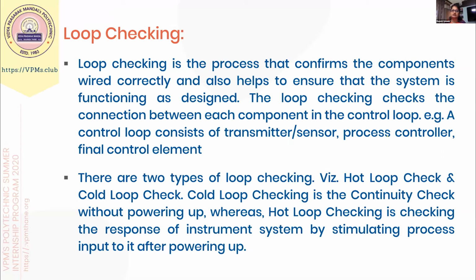The loop checking checks the connection between each component in the control loop. That is, a control loop consists of a sensor, the process controller and the final control element. So whether the loop is working in the right manner, that is being checked in the loop checking. There are two types of loop checking. One is cold loop check, second is hot loop check.